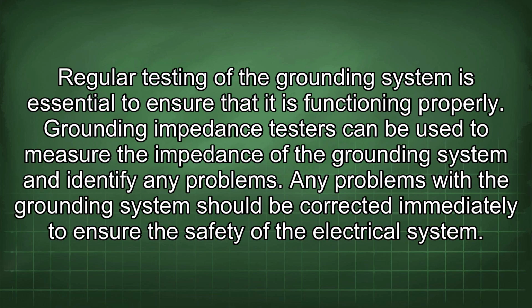Regular testing of the grounding system is essential to ensure that it is functioning properly. Grounding impedance testers can be used to measure the impedance of the grounding system and identify any problems. Any problems with the grounding system should be corrected immediately to ensure the safety of the electrical system.